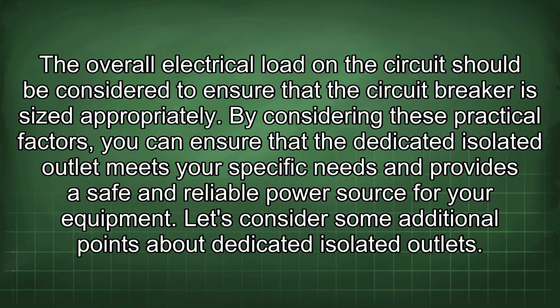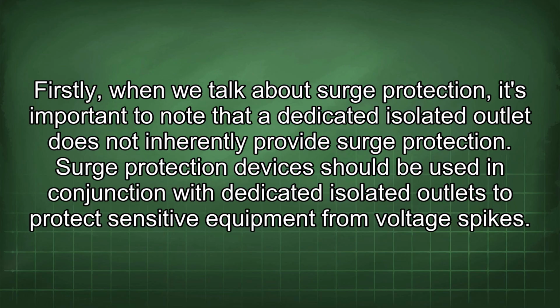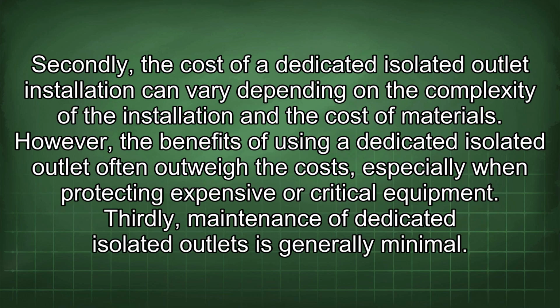Let's consider some additional points about dedicated isolated outlets. Firstly, when we talk about surge protection, it's important to note that a dedicated isolated outlet does not inherently provide surge protection. Surge protection devices should be used in conjunction with dedicated isolated outlets to protect sensitive equipment from voltage spikes. Secondly, the cost of a dedicated isolated outlet installation can vary depending on the complexity of the installation and the cost of materials. However, the benefits of using a dedicated isolated outlet often outweigh the costs, especially when protecting expensive or critical equipment. Thirdly, maintenance of dedicated isolated outlets is generally minimal.